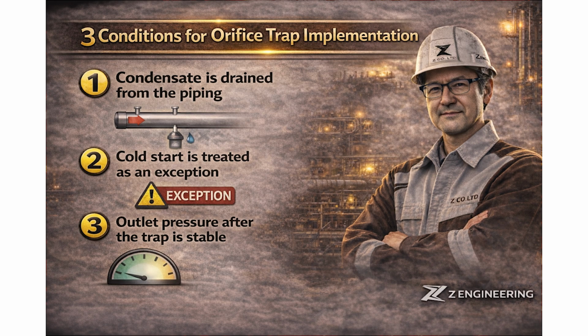Let us summarize. Whether an orifice trap works in a factory depends mainly on 3 conditions. First, condensate must be properly drained from the steam piping. Second, blow-off must be performed during cold start. Third, the back pressure after the trap must remain stable. If these conditions are not satisfied, it is often safer not to choose an orifice trap.